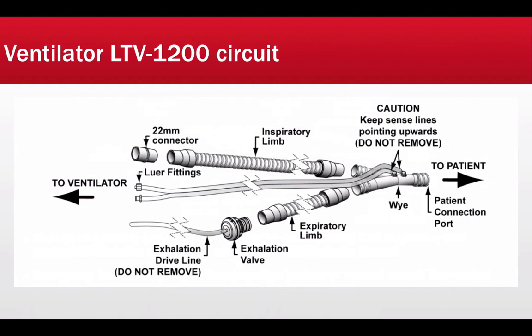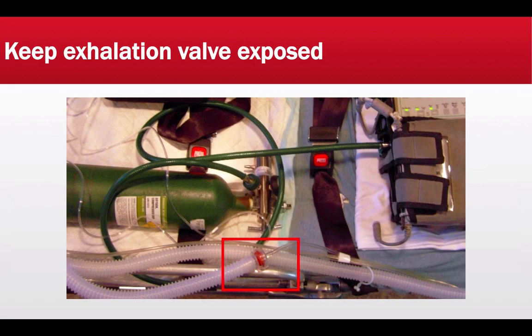Here is another picture of the LTV circuit with all parts distinct from each other. At the top of the Y are the sense lines — keep them pointing up toward the ceiling, not toward the floor. They connect to the ventilator via luer fittings and are color-coded. The exhalation valve also connects to the ventilator and provides important data such as exhaled minute ventilation and exhaled tidal volume. The exhalation valve, shown in the red rectangle in the close-up picture, must remain exposed.